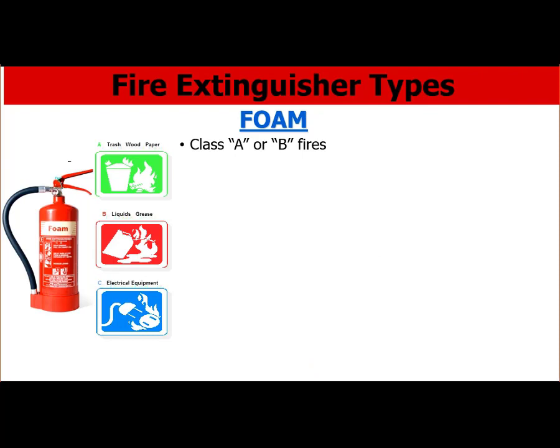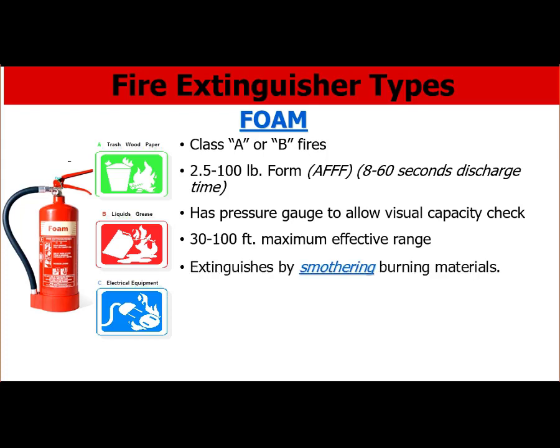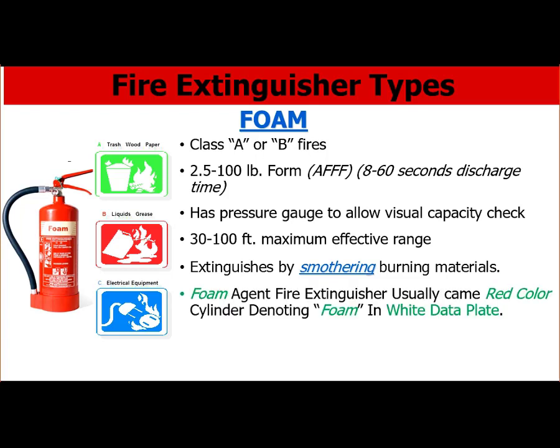Foam type fire extinguishers, also called Aqueous Film Forming Foam (AFFF), are used for Class A and Class B fires. General capacity is 2.5 to 100 lbs and they last up to 8 to 60 seconds of discharge time. Like DCP and water, they have a pressure gauge to check condition. They have a maximum effective range of 30 to 100 feet and extinguish fire by smothering, similar to DCP and CO2. They usually come in a red cylinder with 'foam' denoted in a white data plate.